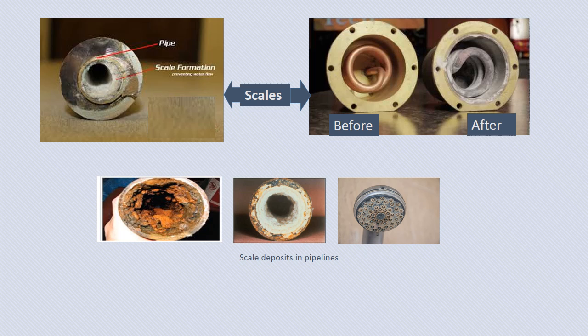Here you can see in the next view, the first one is a very clear picture before utilizing any boiling in it. It's a heater, a heating coil, and see once it has been used, what is the level of deposit found in the boiler. To distinguish, the first one is also because of corrosion, not only because of deposit, it also started corroding here. And the next one is purely, you can see the white portion is a scale deposit. Here it is corrosion cum deposits.